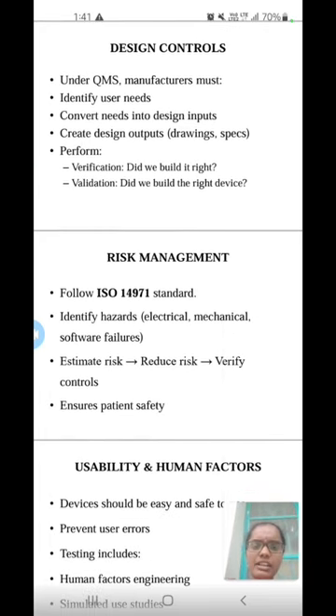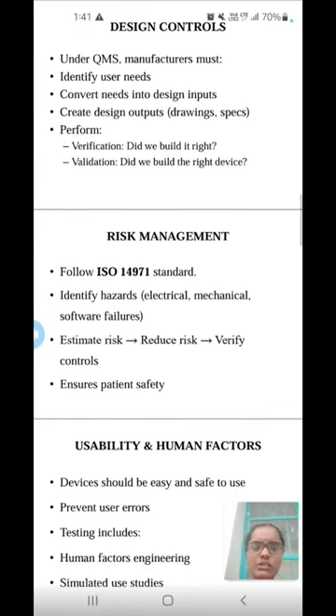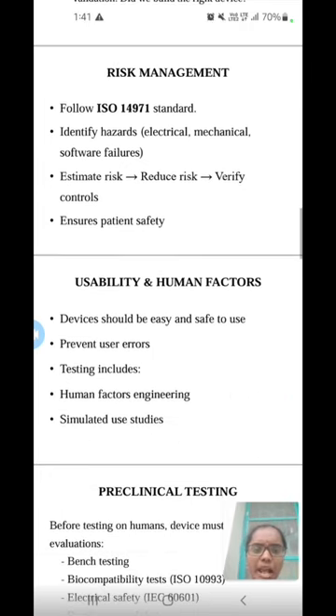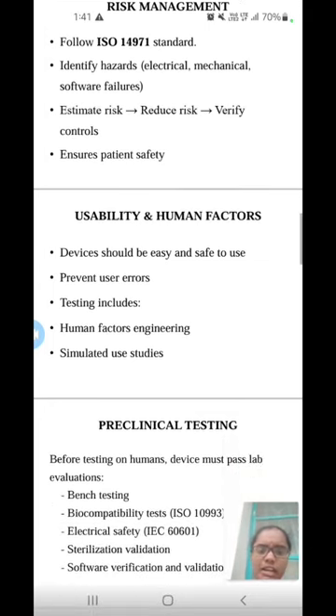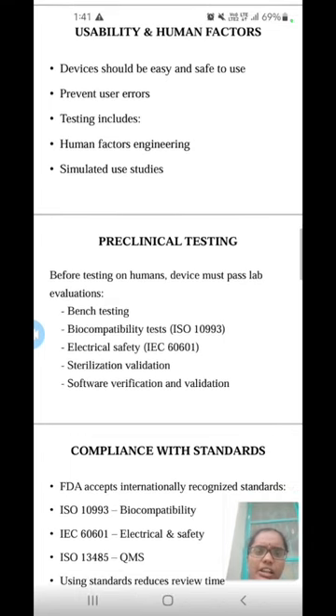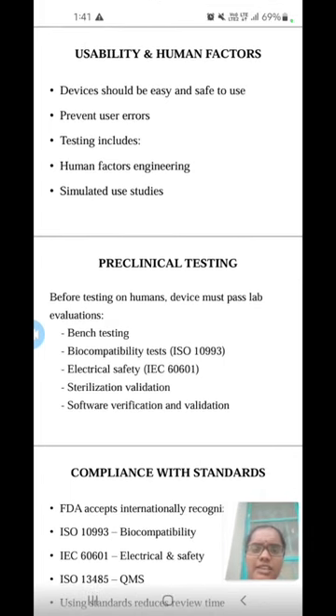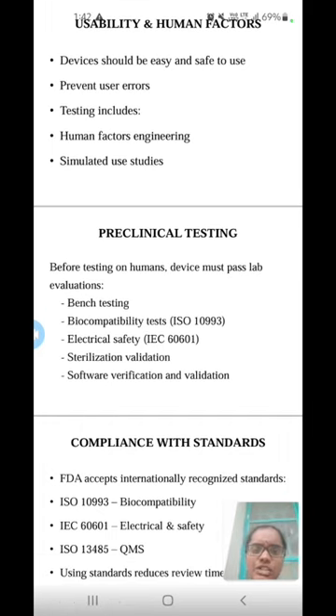Design controls. Under QMS, the manufacturer must identify user needs, convert needs into design inputs, create design outputs, and perform verification and validation. Risk management: follow the ISO 14971 standard, identify hazards, estimate risk, reduce the risk, and verify controls. Ensure patient safety, usability and human factors. Devices should be easy and safe to use and prevent use errors. Testing includes human factors engineering and simulated use studies.